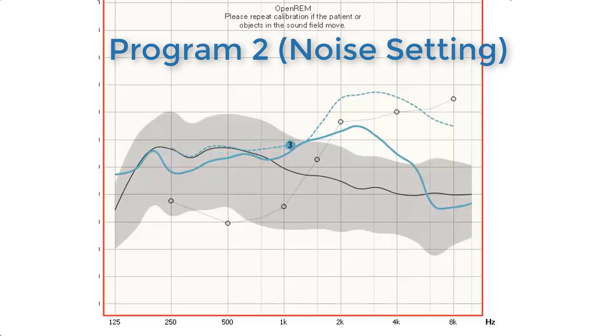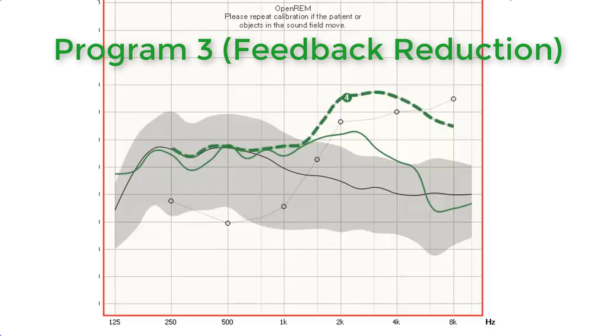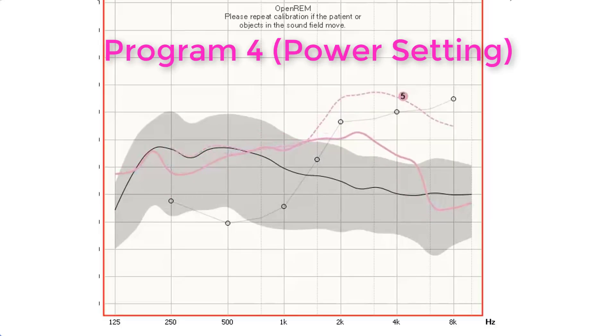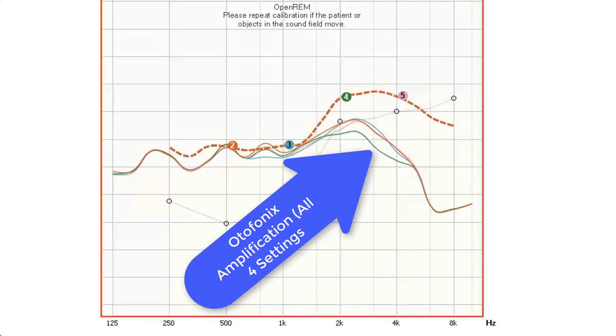Program 2, also known as the noise setting, is designed to reduce background noise and is illustrated by a solid turquoise line. In this setting, it is reducing some of the mid-frequency amplification. Program 3, illustrated by the green line, is designed to reduce feedback — that whistling sound from poorly fitted hearing aids. In this setting, the high-frequency amplification is reduced to limit sound leaking from the dome and cycling back through the microphone. Finally, Program 4, the pink line, is known as the power setting, designed to increase volume for things like watching television in a controlled environment. When we overlap all four program curves at default volume, they are all similar except for Program 3, which reduces the high-frequency amplification.